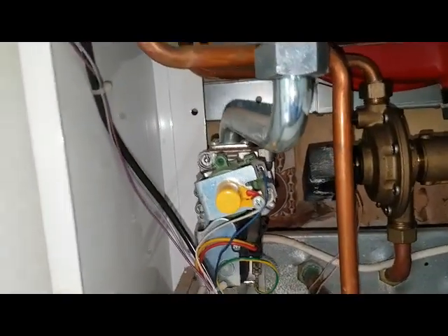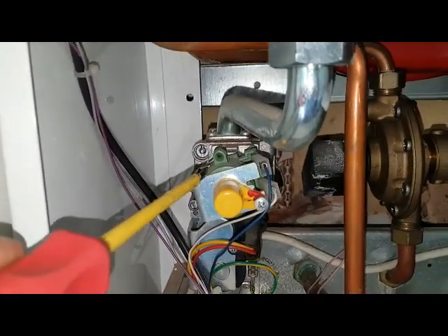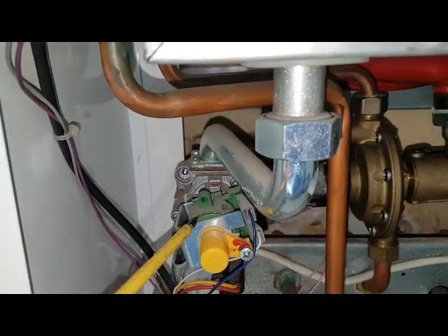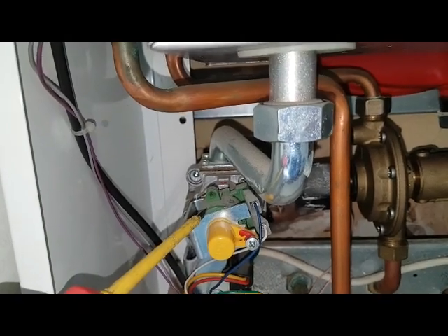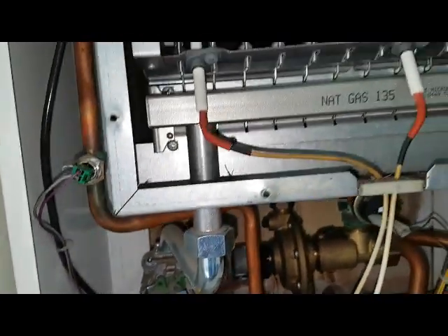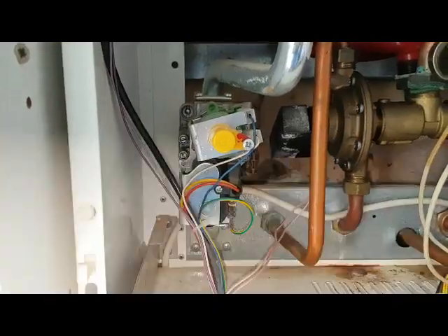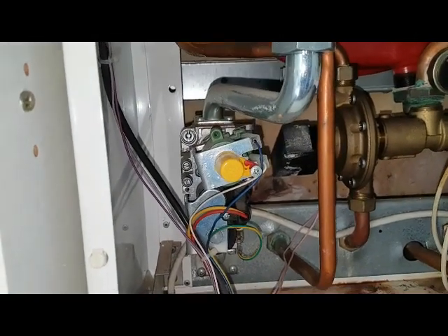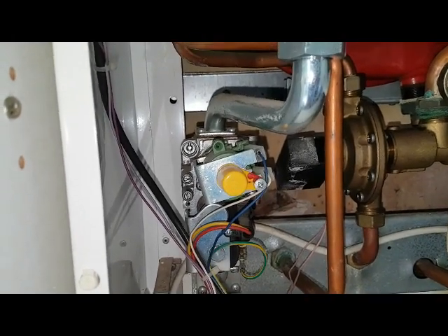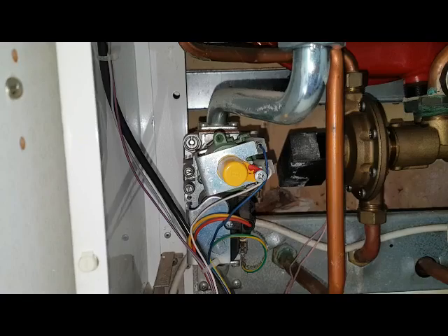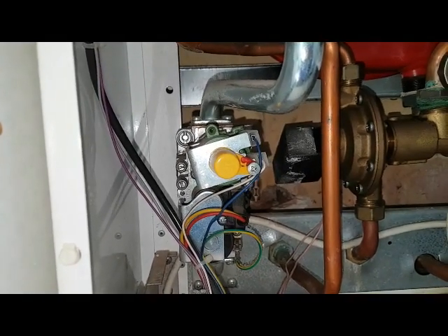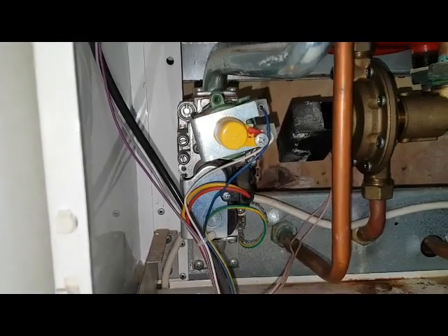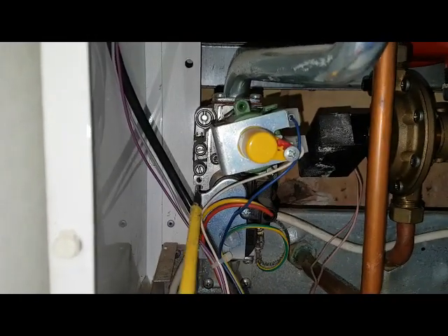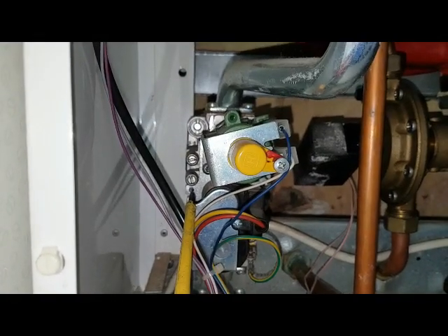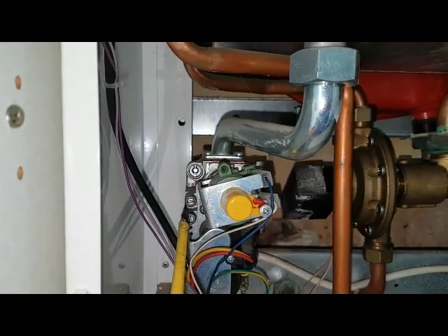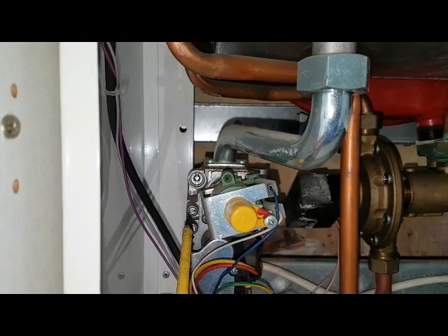To do the modulation, it's done through this part of the gas valve, this green part, that's called a modulating coil. That then governs the high and low gas to the burner. Also on the gas valve, this is for people doing gas portfolio, who want to know a bit more about the working pressure and burner pressure. Your working pressure is taken from the inlet, that's the one at the bottom, and your burner pressure is the outlet, taken from the top one.